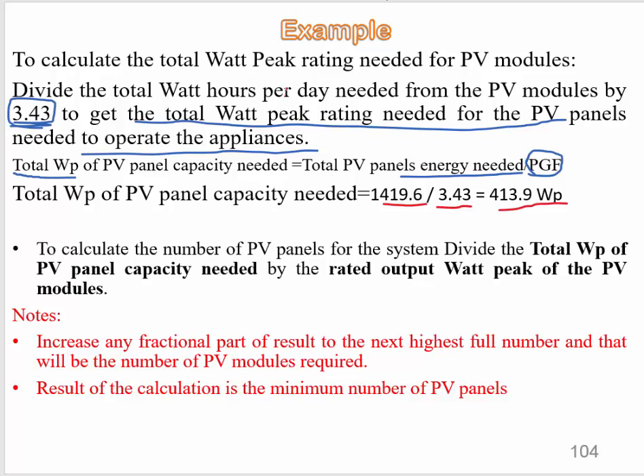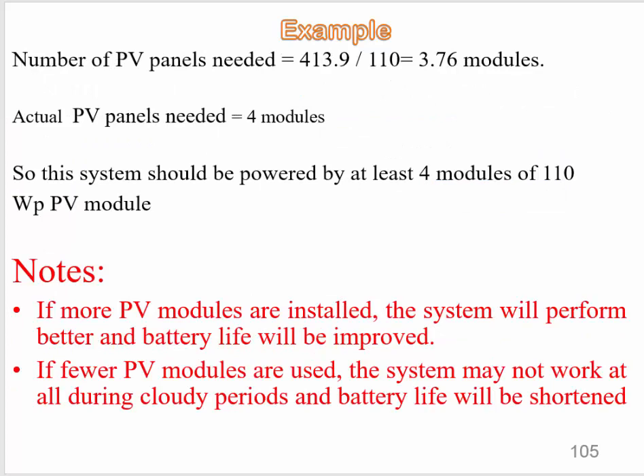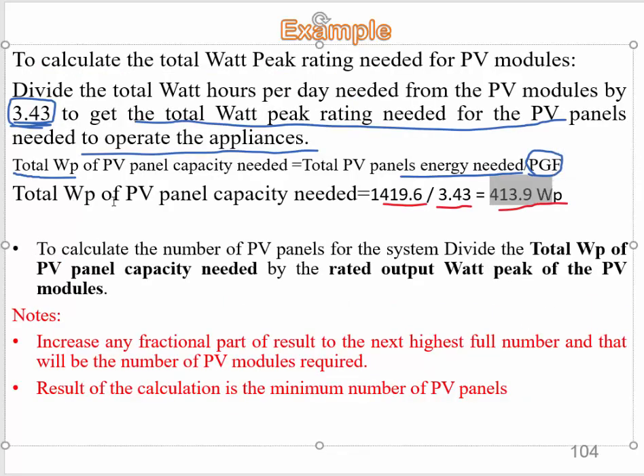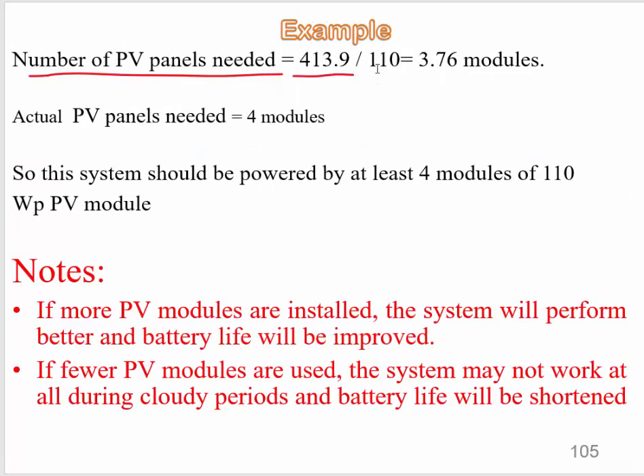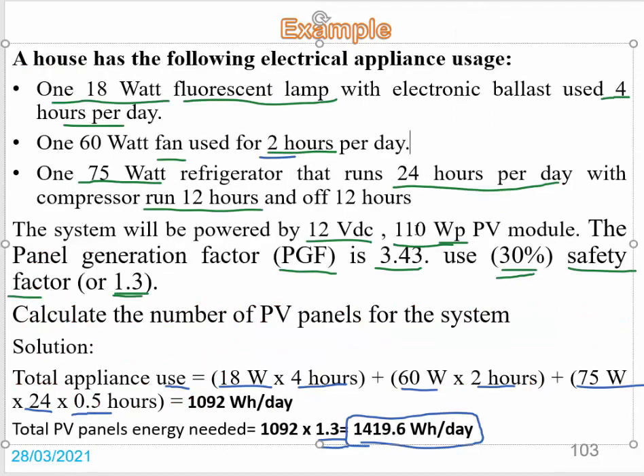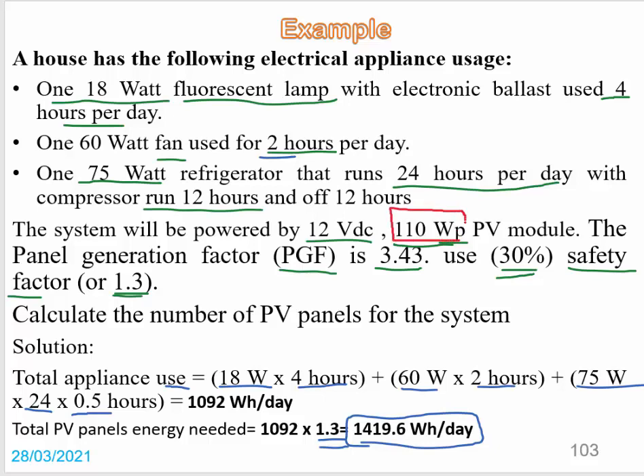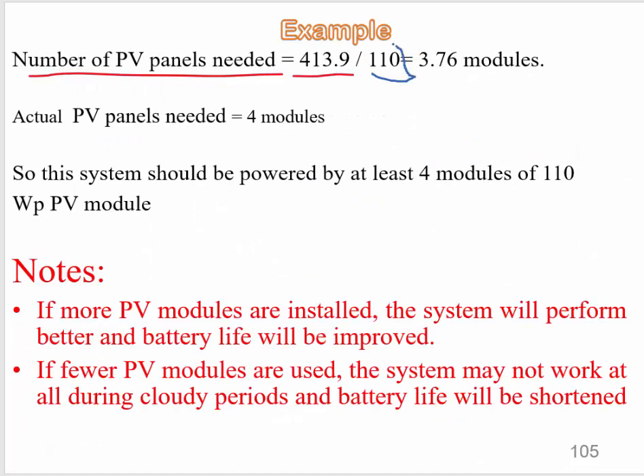To calculate the number of PV panels needed, we divide the total watt peak of PV panel capacity needed by the rated output watt peak of the PV modules. There are two notes: first, increase any fractional result to the next highest whole number; second, the result is the minimum number of PV panels required. We divide 413.9 by 110 Wp, since each solar panel provides 110 watt peak.